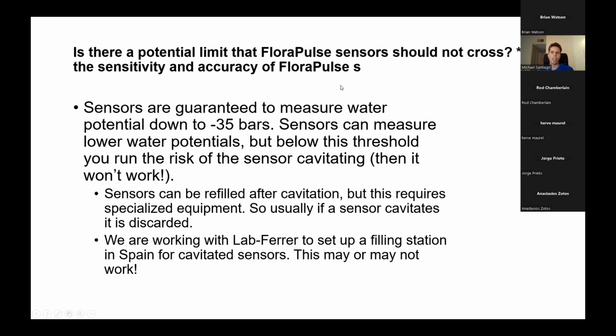There's a potential limit the sensor should not cross - I'm not totally sure about the rest of that question, but we guarantee the sensor to measure down to minus 35 bars, because that's what we test - every sensor can go down to minus 35 bars. They can often measure lower water potentials, but below this threshold you run the risk of the sensor cavitating.